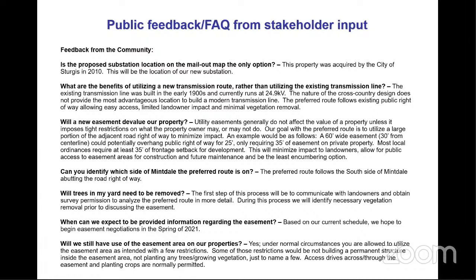If we design and build a transmission line based on what's currently there, and then a landowner builds maybe a shed or a garage inside that easement, now they're negating the clearances we built to maintain. There may be a horizontal or vertical clearance we're required to maintain, and building a permanent structure in the easement would violate those clearances. So part of the negotiations and the easement language prevents permanent structures being built in the right of way. Similarly with vegetation, you may plant a sapling that's 2 or 3 feet tall, but in 15 or 20 years it may be 15 feet tall, and at that point you could be violating our NESC clearances, which is why we acquire an easement to build these transmission lines. Usually access drives and crops have little to no limitations, and that's on a case by case basis depending on the easement language, which we'll discuss when we start negotiating the easements.